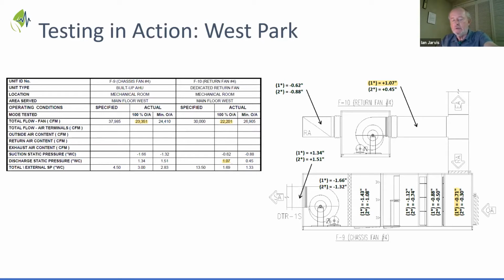So this is one of those that we'll talk about through today that has deteriorated over time. And the return air fan at the same time is running at 22,201. So it's also down significantly. What matters just as much is how different that is during both the 100% outside air relative to design. So the design says that we were looking for 8,000 CFM more supply than return to ensure we have adequate pressurization. During 100% outside air, we're down to only 1,000.